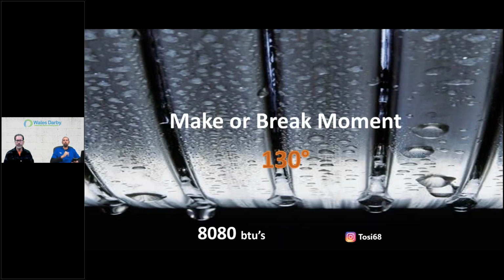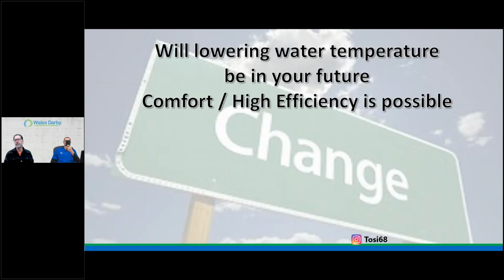All right, make or break right there. That's a good picture. I want that 8,000 BTUs back. How do I start to achieve that? Well, 130 and less return water to that piece of equipment. Make or break moment. So will lowering water temperatures be in your future? Comfort and high efficiency is possible, I promise you that. A BTU is a BTU. What do you need to deliver? And these are what we have as options for emitters. Even with lowered water temperature, they still deliver high BTU outputs. We're all good.